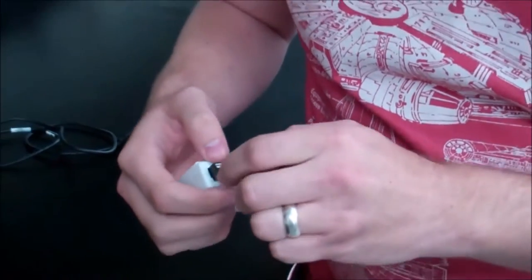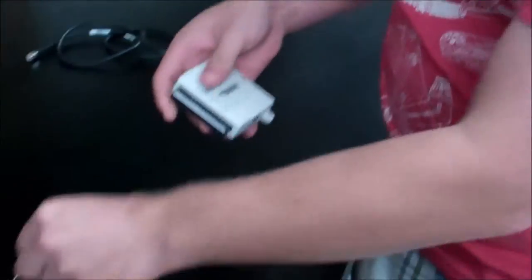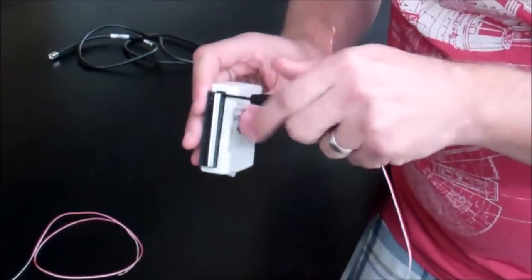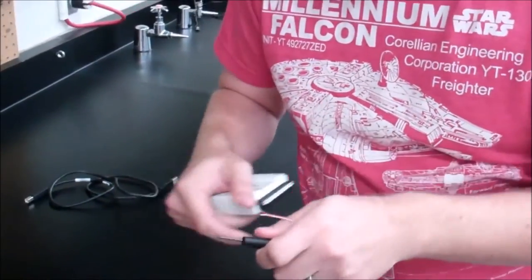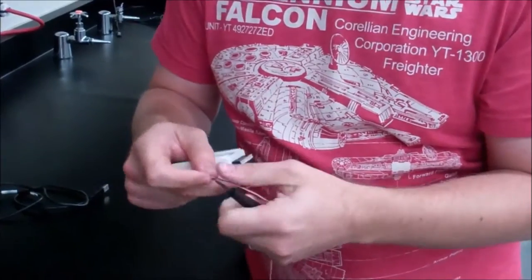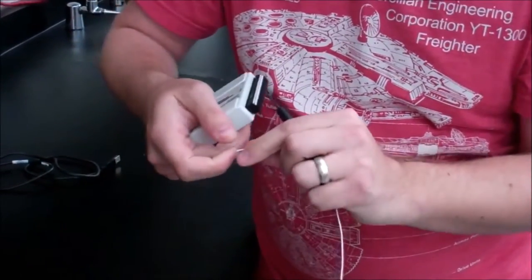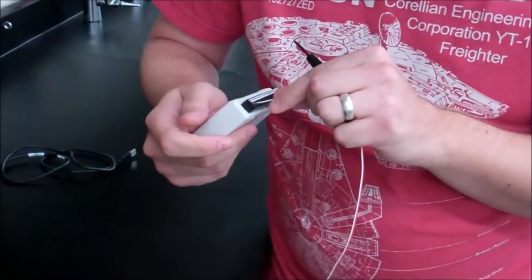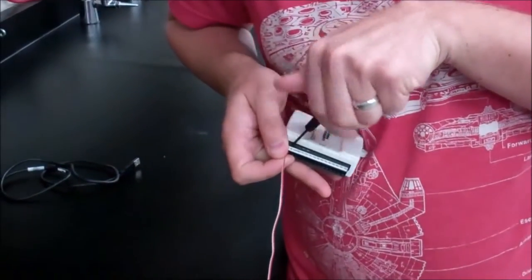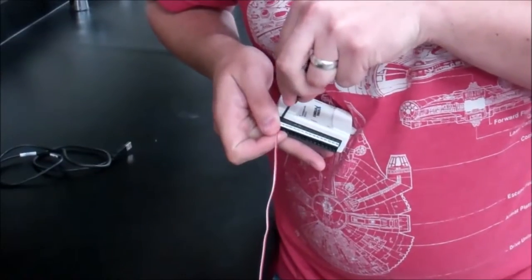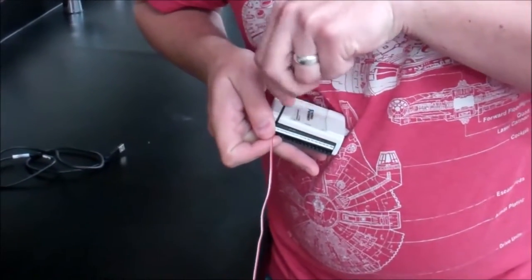This is going to supply the power to our Wheatstone Bridge circuit. You need to make sure that you have all of the accepting connectors to the DAQ down so you can put the wires in. Put the wires in and tighten them. Make sure it's nice and tight.